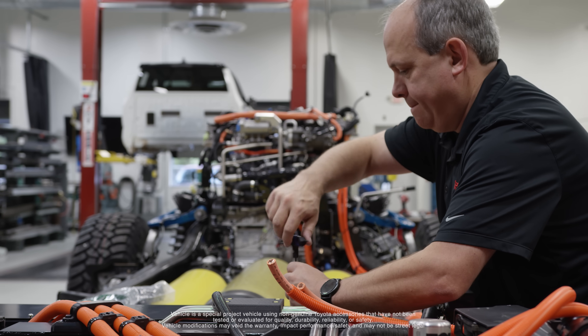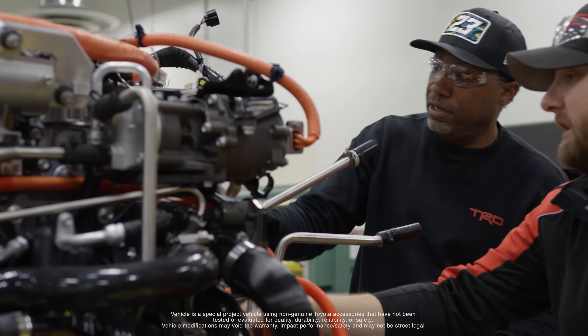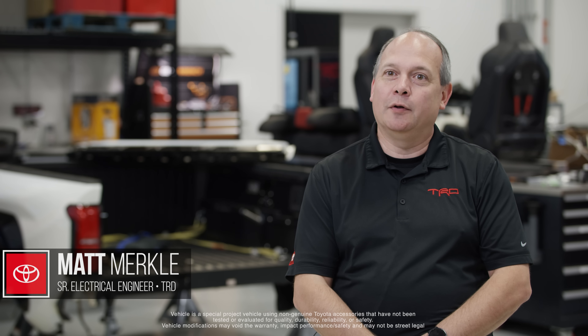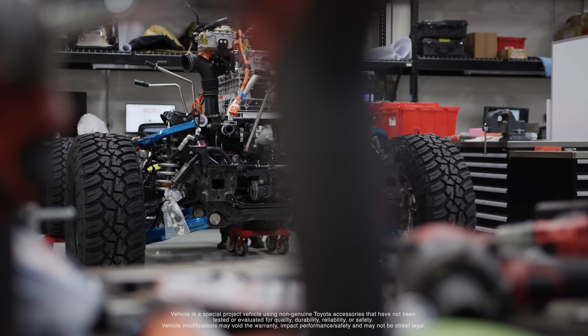Doing a lot of the wiring, there are a lot of connections — if you just want to do a quick, haphazard job of it you can knock those out quickly, but if you want to do it right, make sure they're weatherproof, make sure they're documented, make sure they're labeled, it probably takes two to five times longer than to just get it done.